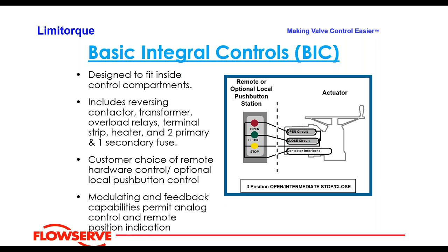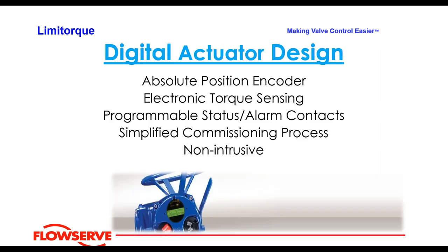These electromechanical actuators typically have what's called basic integral control inside the control box: a transformer, reversing contactor, terminal strip, heaters, and fuses. All you have to do is bring in your power supply and discrete control. If you want to position with it, a modulating feature for 4–20 mA control in and 4–20 mA control out can be added. Over the last 20 years, a lot of actuators and process equipment have become digital-based, because we can get so much more information to make decisions — whether for preventative maintenance or precise process control.